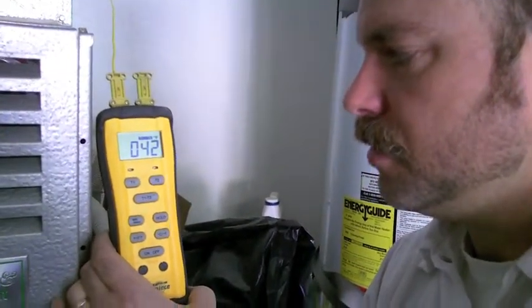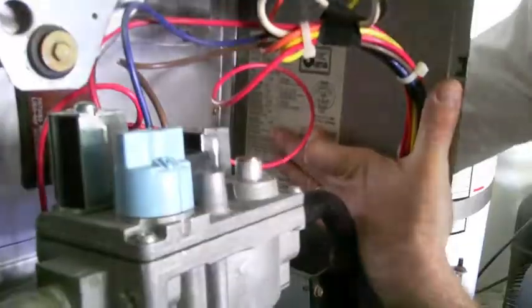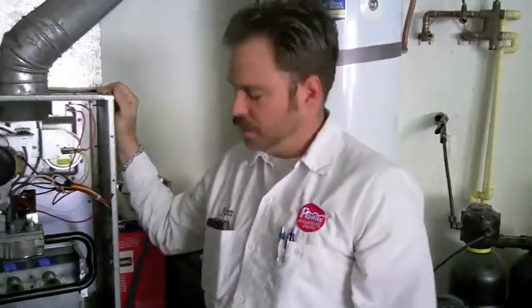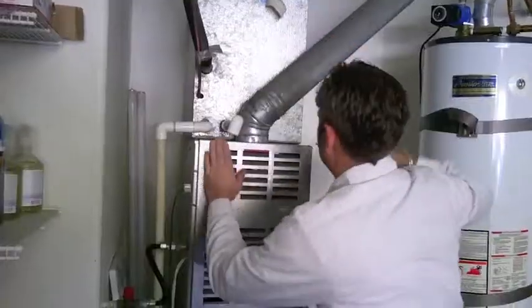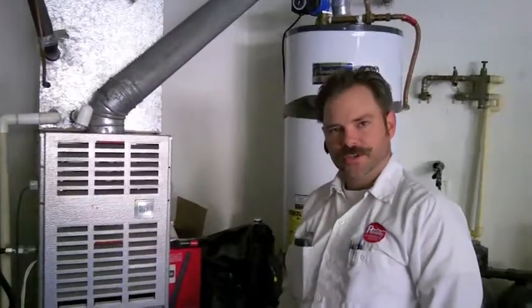Which is about 42. And this one says between 15 and 45. So this one's a little bit on the high end. Normally I would look for a dirty air filter or vents inside the house which are shut off. There you go. That's your furnace service.